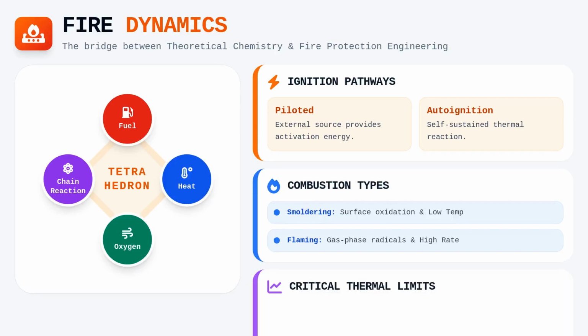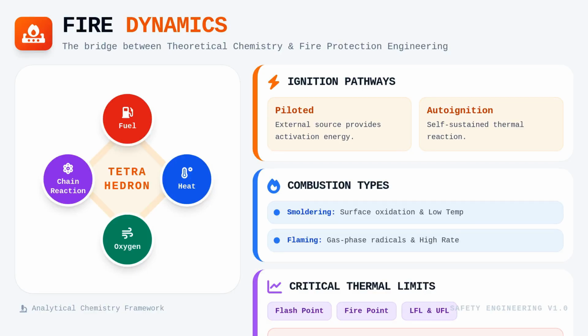Understanding these phenomena requires us to look at the transition points, such as the flash point and fire point, which dictate the specific temperature at which a liquid fuel generates sufficient vapor to support ignition or sustained burning. We must also rigorously quantify the limitations of combustion by identifying the lower and upper flammability limits, which define the concentration range in which a fuel-air mixture can actually propagate a flame. Without these precise data points, any attempt to predict fire behavior in a real-world building scenario remains strictly speculative and scientifically unsound.